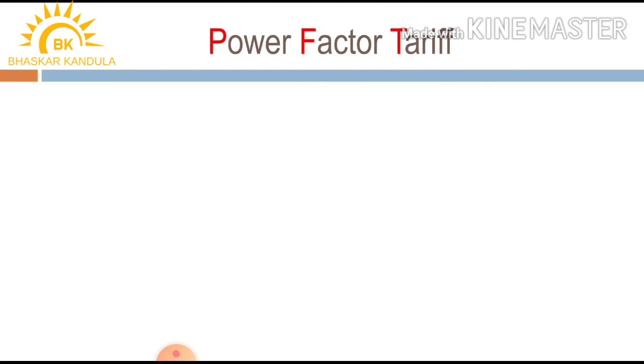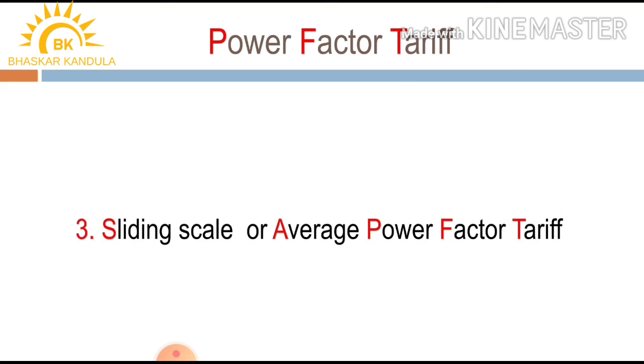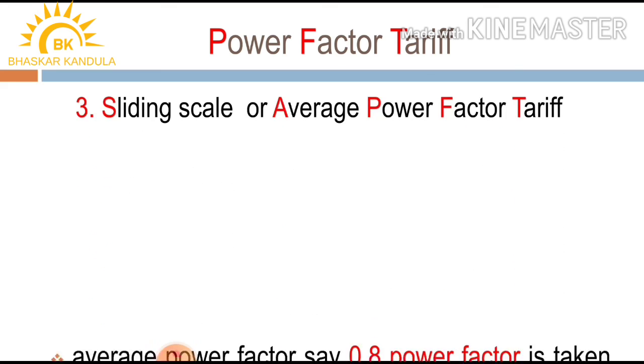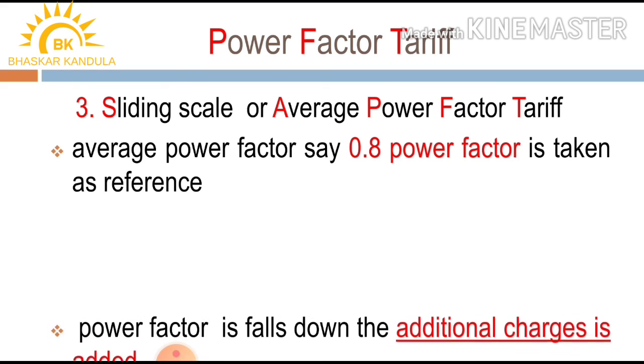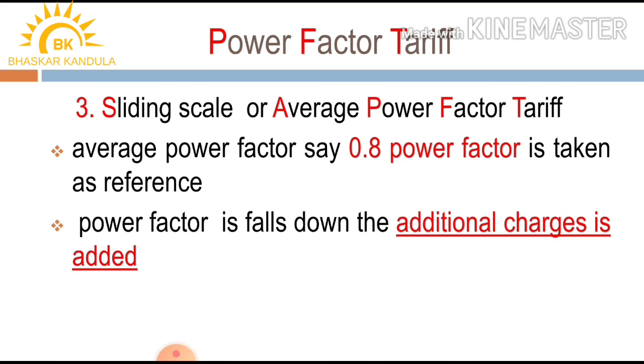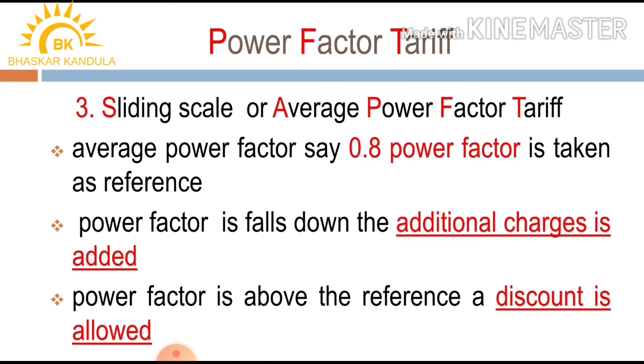In the sliding scale or average power factor tariff, an average power factor of 0.8 is taken as the reference. When the power factor falls below the average value of 0.8, additional charges are added. If the power factor is above the reference value, a discount is allowed to the consumers.